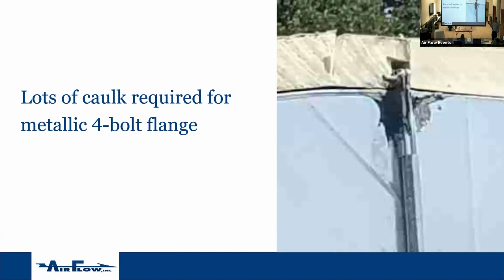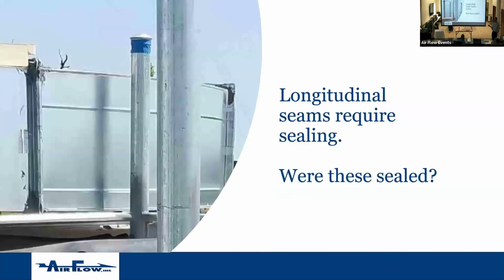Now you can see this particular one, there's a lot of caulk. Maybe that's good. Maybe it's not good. Did the longitudinal seam, now we talked about high pressure ductwork, so you've got to see, there's no wall penetrations in high pressure ductwork on a roof. Generally, there may be T's, or not taps, but T's, right? You may have a branch going into different openings through a roof penetration. But did this horizontal longitudinal seam get sealed? Hopefully. You're never going to see it. Never going to know, right? When we see the Ventureclad bubbling out, we might have an idea of whether it got sealed or not.